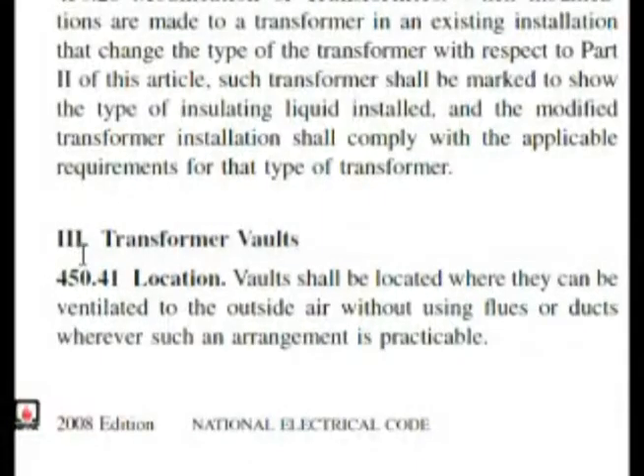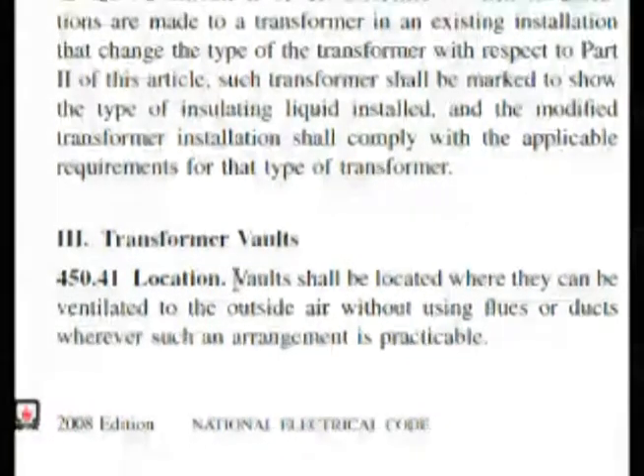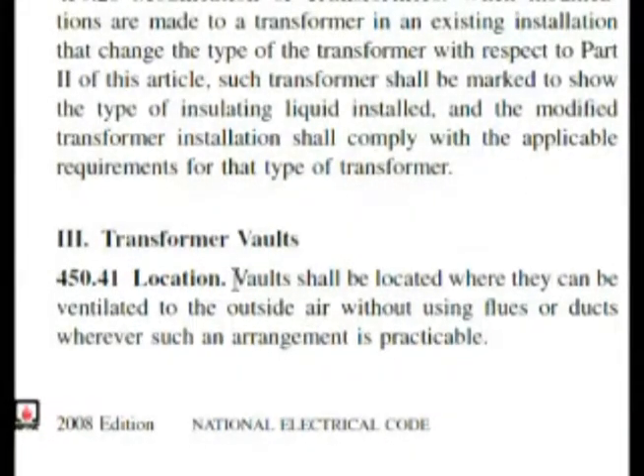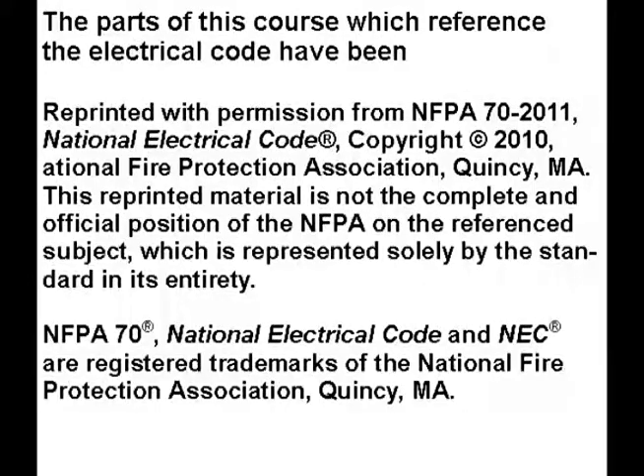Here we are at 450 Roman numeral 3, transformer vaults. The question was asking about a location, and we have here almost word-for-word: transformer vaults shall be located where they can be ventilated to the outside air without using flues or ducts wherever such an arrangement is practicable. Practicable is answer B on our exam.